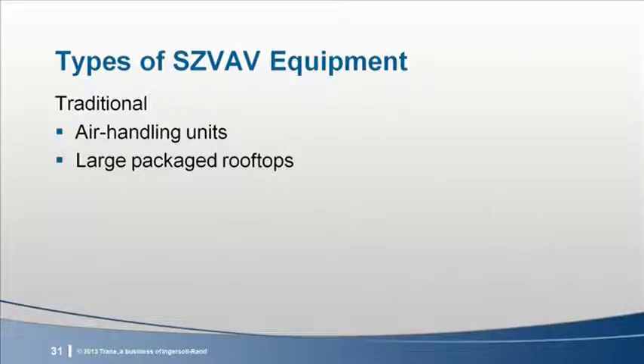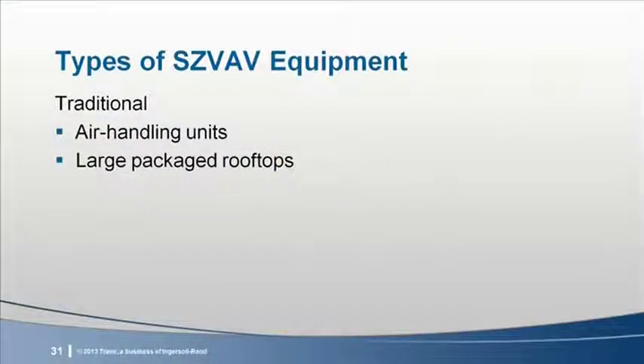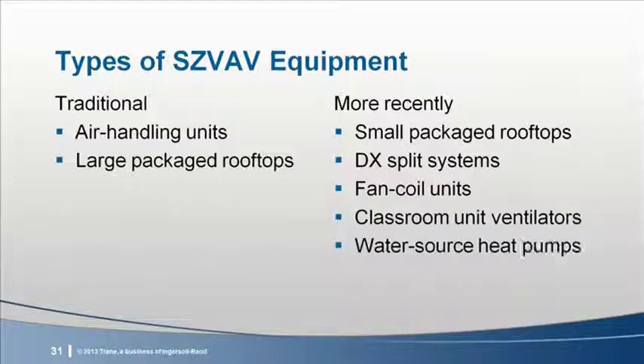Since single-zone VAV was traditionally used in those larger type zones, it's been available primarily in large air handling units and large package rooftop equipment. This type of equipment has been available for years with variable speed fans and cooling and heating that can be staged or modulated to control discharge air temperature. However, as single-zone VAV has become more popular for the smaller zones found in schools, stores, and offices, we're starting to see this functionality offered in smaller equipment. Equipment like small package rooftops and DX splits, fan coils, and classroom unit ventilators, and even water source heat pumps, which we discussed in our E&L program last summer.